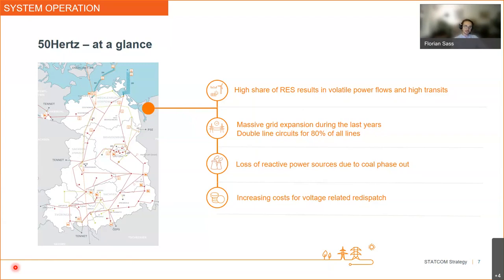In addition to increasing transits, in addition to this grid expansion, we are facing a severe loss of reactive power sources due to the coal phase out. This means, especially in the eastern part, in a region that we call Lausitz, which has been a coal-fired or even lignite-fired region for almost 100 years, there is the phase out of coal. We are losing production capacity regarding active power, but also regarding reactive power. So the sources of reactive power production are somehow lost and only provided in parts by the renewable energies, since they are placed in the northern part and not in the high transit area of the south.